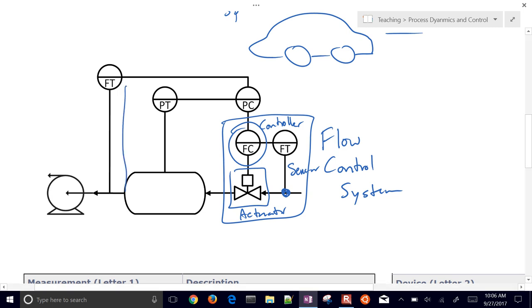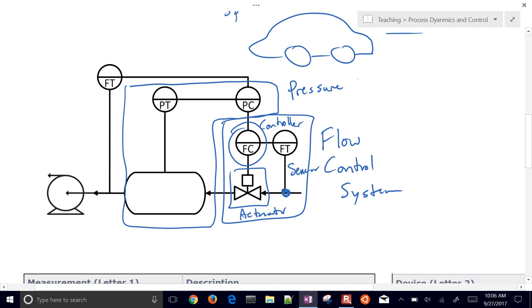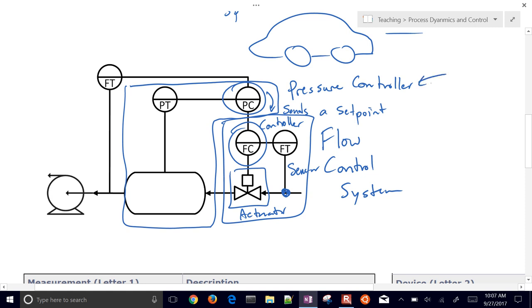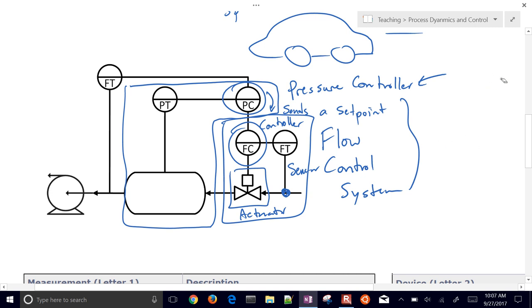We can also have more complicated control schemes. For example, a pressure control system where instead of writing directly to a valve, the pressure controller sends a setpoint to the flow controller. This is called cascade control. The pressure controller is the master and the flow controller is the slave. There are different layers or hierarchies: the pressure controller sends a setpoint signal to the flow controller, which tries to follow it.